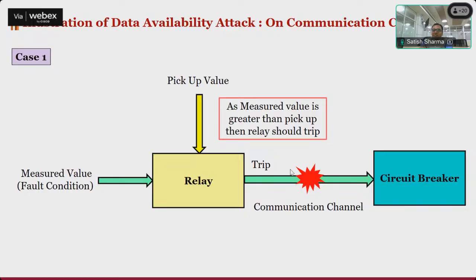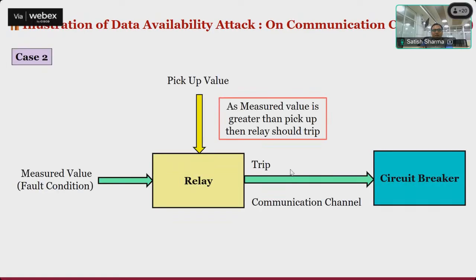delayed, and it may lead to other parts, or basically other equipment in the system, being under overload, and maybe the primary protection does not work. In that case, the secondary protection will come into the picture, and that will isolate more, an increased size of the network will be isolated in that particular case. So whether it is a delay attack or a DOS attack, either can be there.